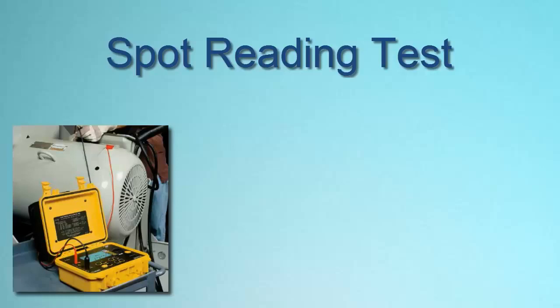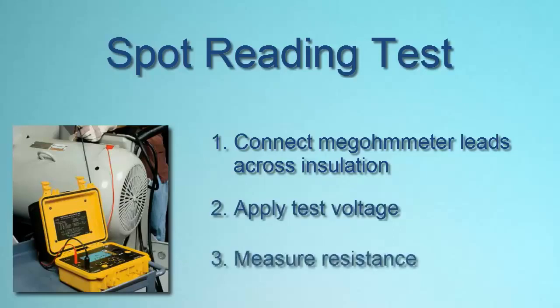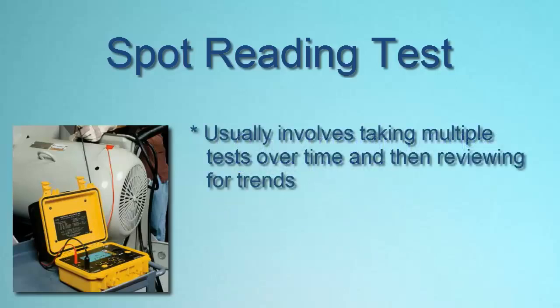The first type of insulation resistance test we'll look at is the spot reading test. This is relatively straightforward. Simply connect the megohmmeter leads across the insulation to be tested, apply test voltage for a fixed period of time, typically 1 to 10 minutes, and then take a resistance reading. Spot testing is suitable for a system with small or negligible capacitive effect, for example a short wiring run. A single spot reading test is of limited value, but the results become meaningful when a series of tests, all featuring the same voltage and duration, are performed over time and the results compared.